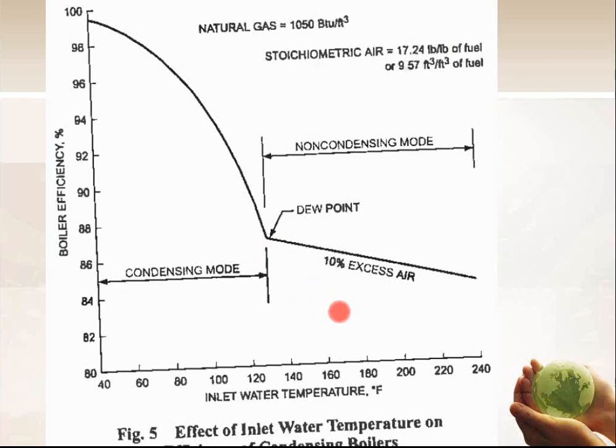And at that point, I don't care how much it condenses. In fact, I want it to condense. And the colder the water, the better. So pretty much the coldest water I could take would be something that's slightly above freezing, because I don't want to pump slush around, right? So for the sake of argument, we'll say 40 degrees is the coldest return water I can get. So if I've got a snow melt system and I'm sending 50, 60-degree water back to my boiler, it loves it. That boiler becomes a 99% efficient boiler.